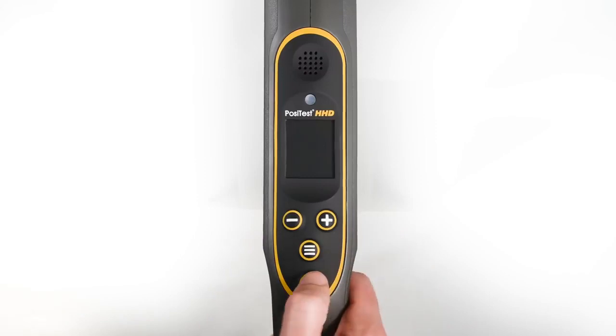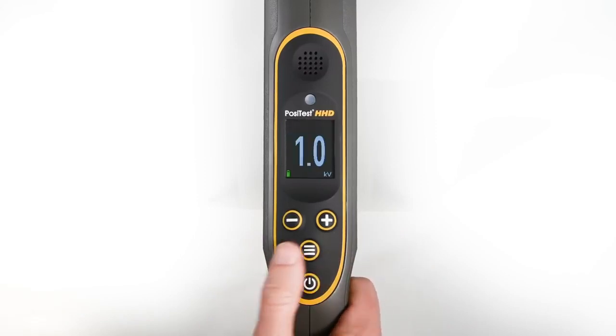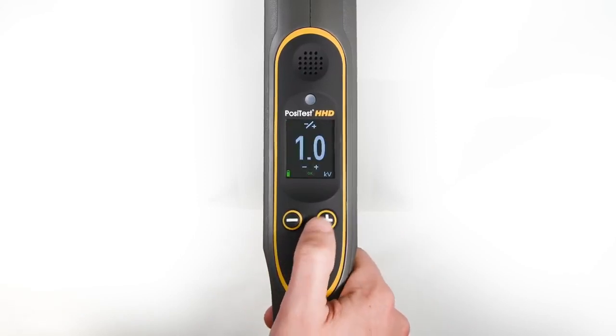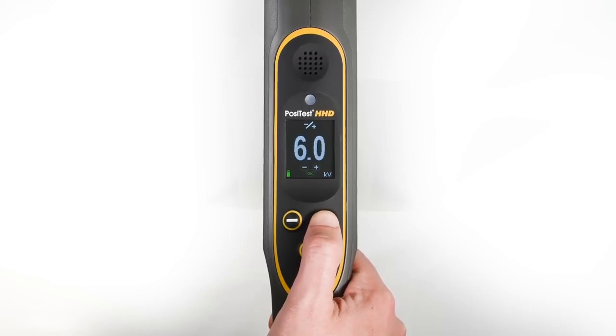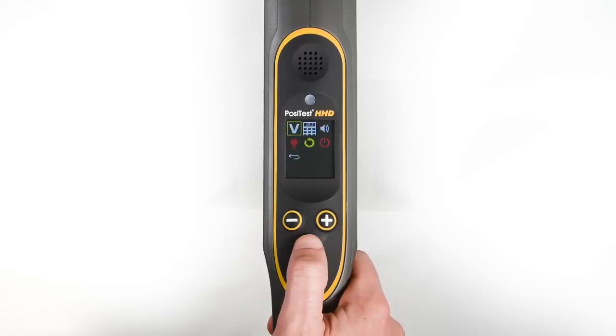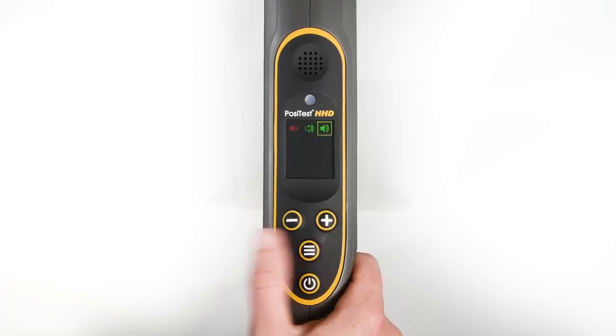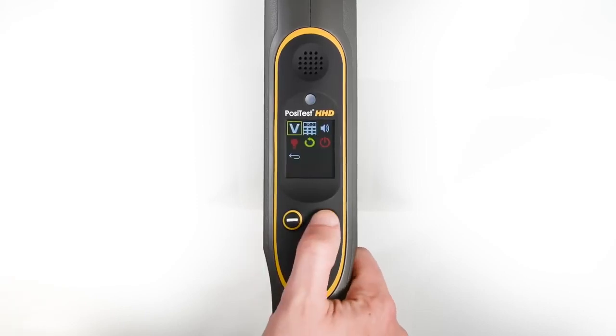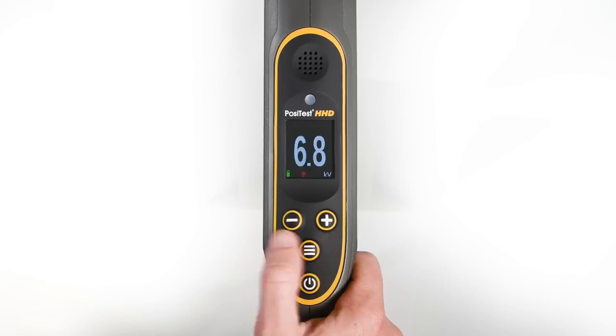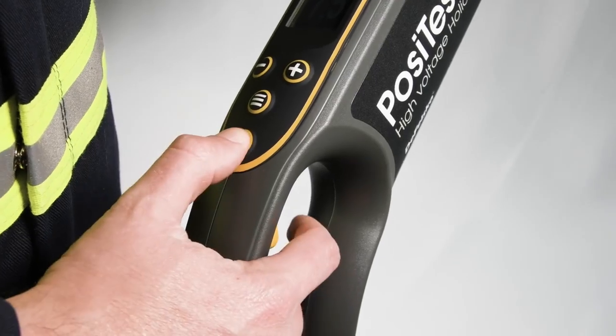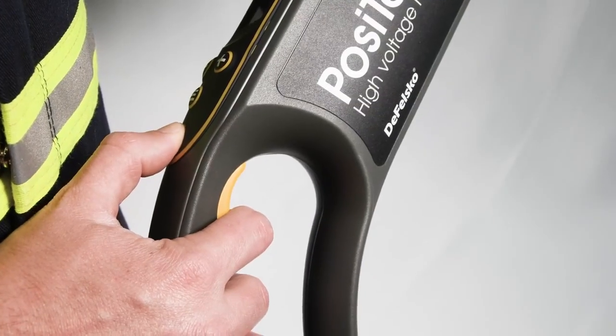Press the power button to turn the Positest HHD on. The set voltage is displayed in the large backlit display, and the icon-based menu can be accessed at the touch of a button to change settings such as the test voltage and alarm modes. Once the test voltage has been verified, begin testing by simultaneously pressing the power button and the trigger.